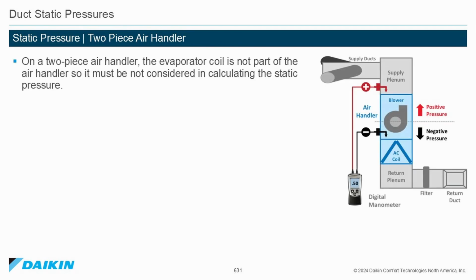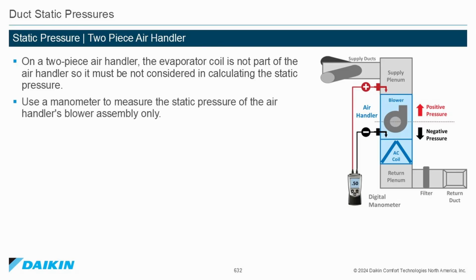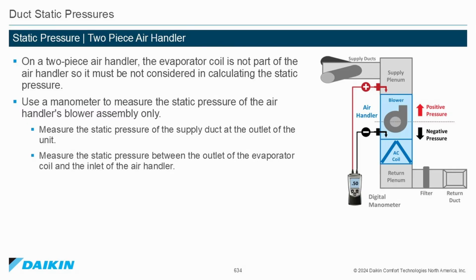Static pressure on a two-piece air handler. On a two-piece air handler, the evaporator coil is not part of the air handler, so it must not be considered in calculating the static pressure. Use a manometer to measure the static pressure of the air handler's blower assembly only. Measure the static pressure of the supply duct at the outlet of the unit. Measure the static pressure between the outlet of the evaporator coil and the inlet of the air handler.